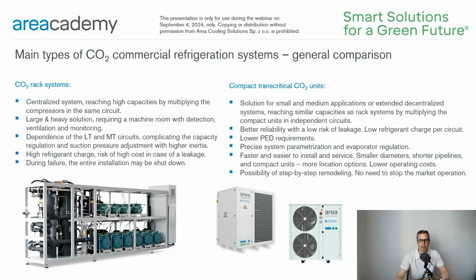CO2 booster systems are centralized systems that can reach high capacities by multiplying the compressors in the same installation. This is a large and heavy solution requiring a machine room with detection, ventilation, and monitoring. In such systems, there is dependence of the LT and MT circuits, complicating the capacity regulation and suction pressure adjustment with higher inertia. The refrigerant charge is large, resulting in risk of high cost in case of leakage. And finally, during failure, the entire installation may be shut down.